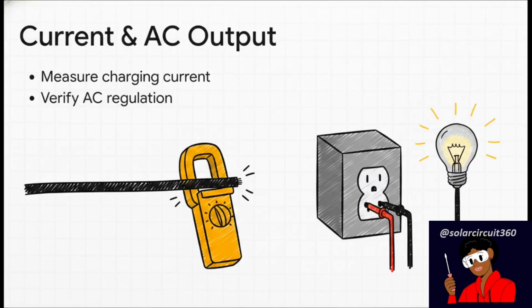For steps 3 and 4, we move over to current and AC output. Using a DC clamp meter, which is great because it measures current right through the wire's insulation, we confirm that energy is actually moving to storage. This is vital. If the sunlight is booming but the charging current is low, your independent clamp meter measurements will reveal array wiring issues or panel performance problems that a simple voltage check just cannot detect. After that, we measure the AC voltage at the inverter output. We aren't just looking to see if the lights turn on, we're verifying that the inverter is providing stable power regulation under an actual real-world load.